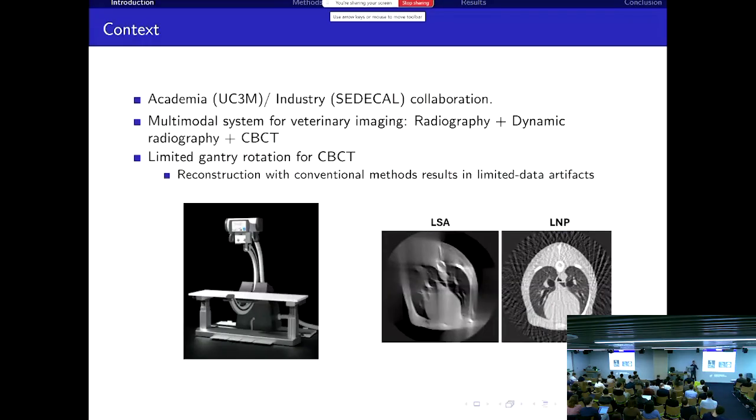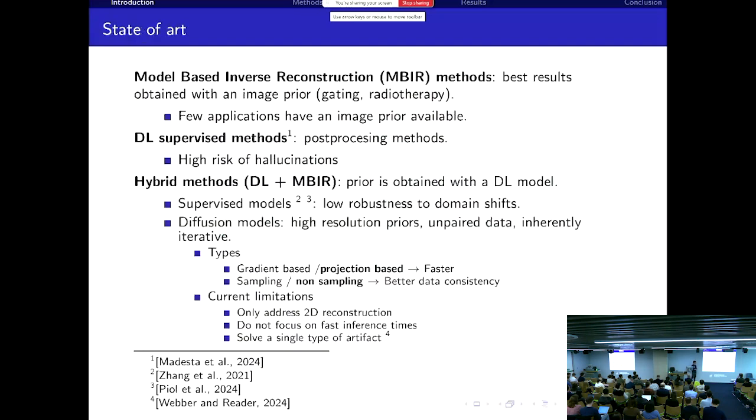Given the hardware configuration of the system, we have a cone beam geometry for the CT acquisition. This means that this is an implicit 3D reconstruction problem. Also, as we have an open gantry, a C-arm, the reconstructed images will have geometrical distortions due to the limited span angle, and also streaks appearing due to the limited number of projections that we acquire in order to reduce the dose applied to the patient. There are many other artifacts, and in fact this is what I've been working on in my PhD, but at the moment we're just going to focus on these two main artifacts.